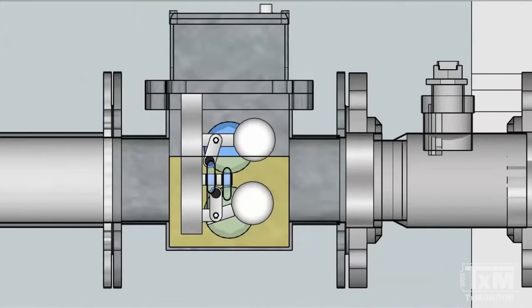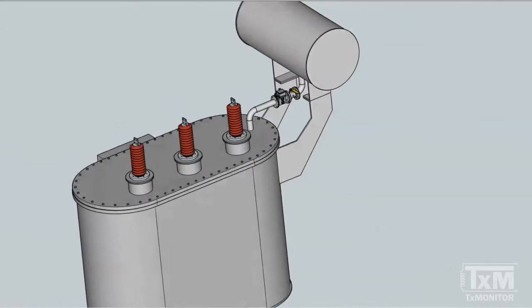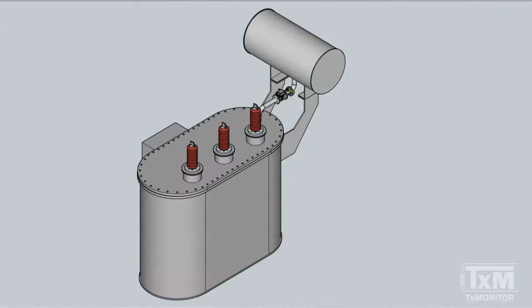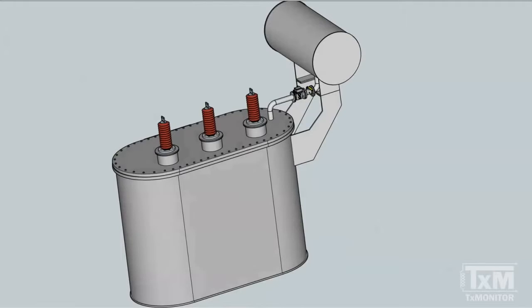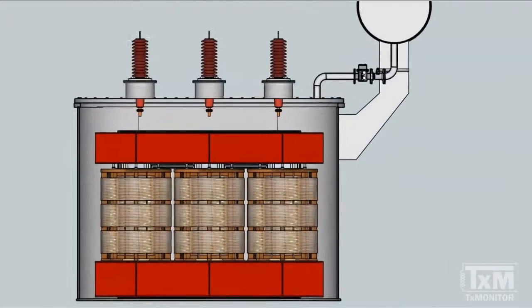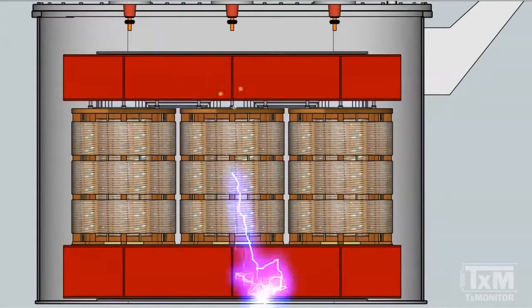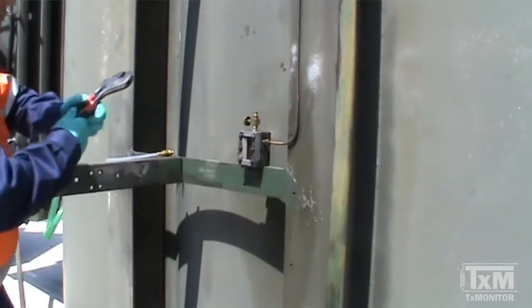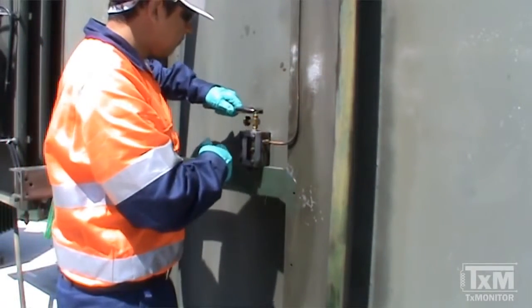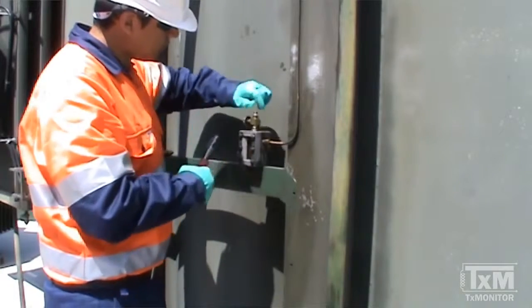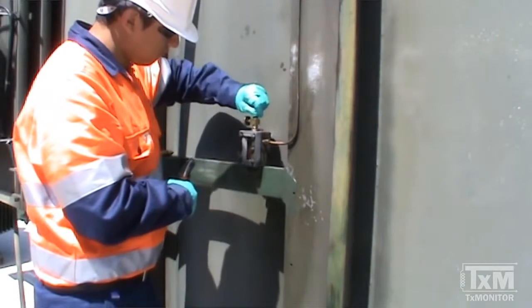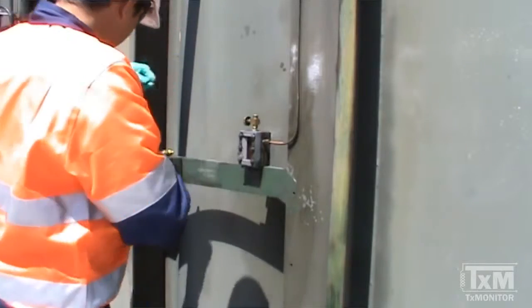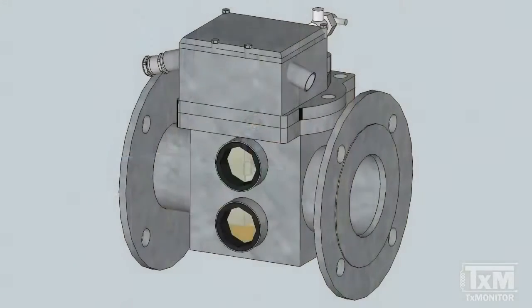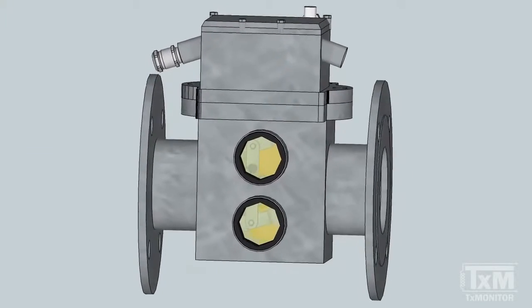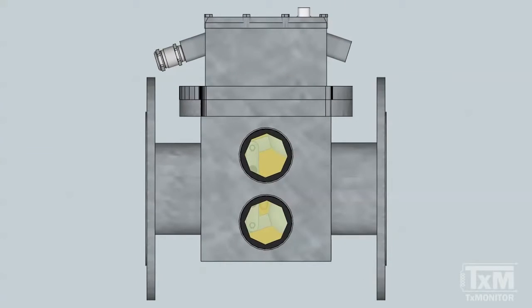It is on this pipe where the Buchholz relay is typically installed to trap the bubbles before they reach the conservator tank. These free gases are commonly the result of abnormal conditions inside the transformer, and are also useful in the diagnosis of these conditions. The Buchholz samples can be taken from the gas sampling device accessible at ground level. If this gas sampling device is not available, the samples have to be taken directly from the Buchholz, and therefore cannot be taken while the unit is energized.